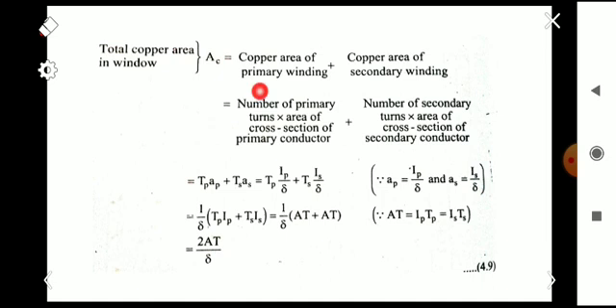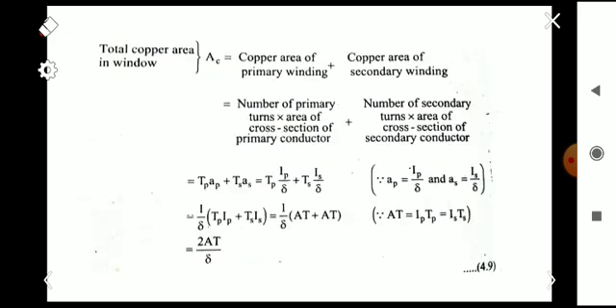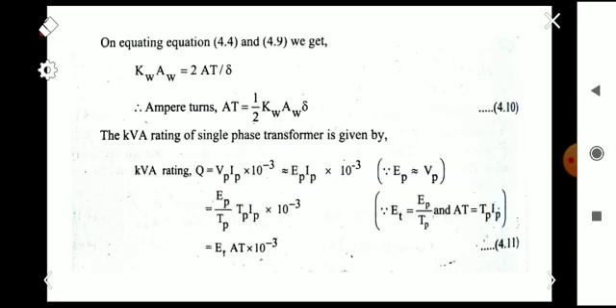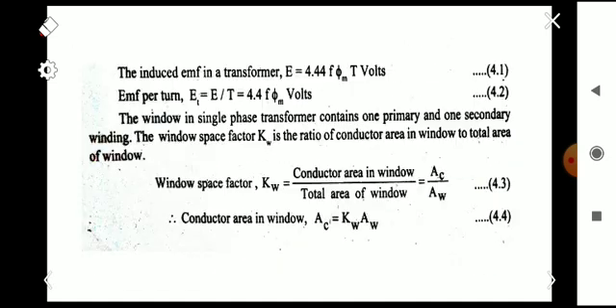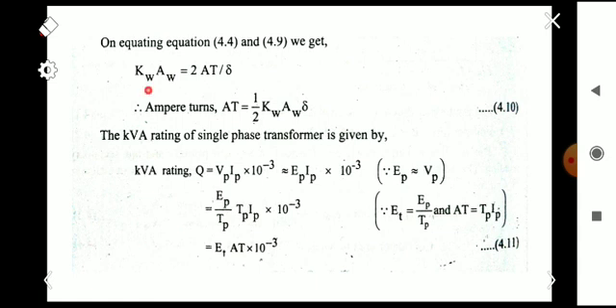Our aim is to compare this derived expression for A_c with the earlier equation. By comparing equation 4.4 (A_c = K_w A_w) with the derived result (A_c = 2AT / δ), we get K_w A_w = 2AT / δ. Therefore, the ampere-turns AT = (1/2) × K_w × A_w × δ.